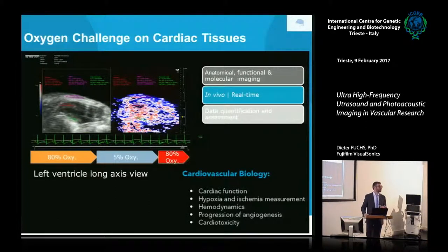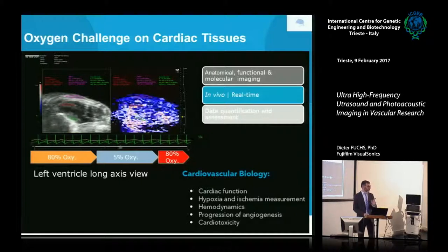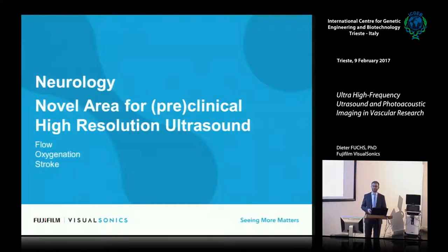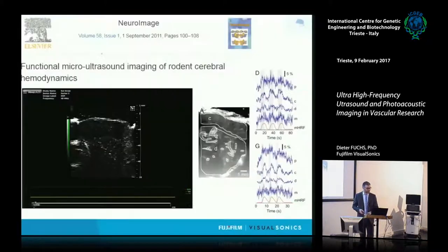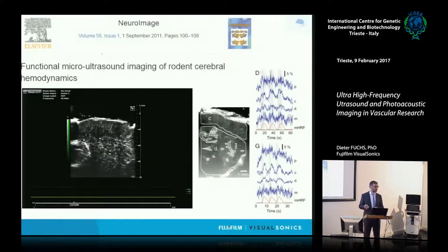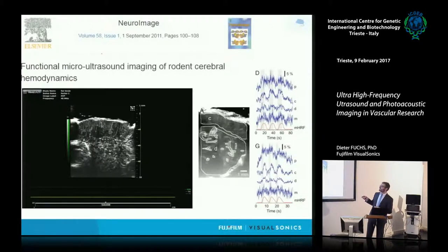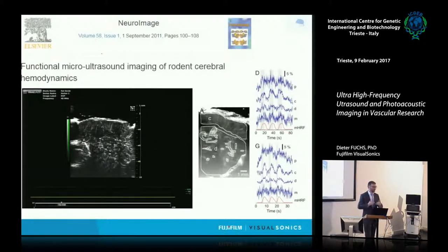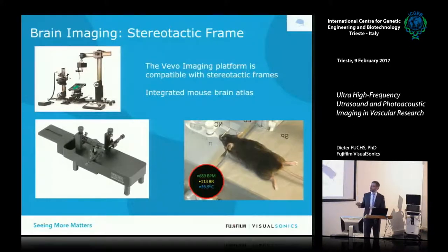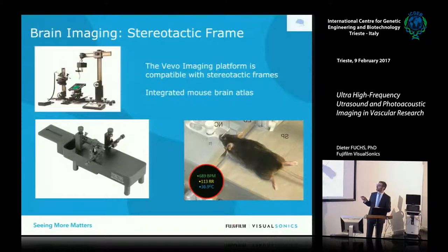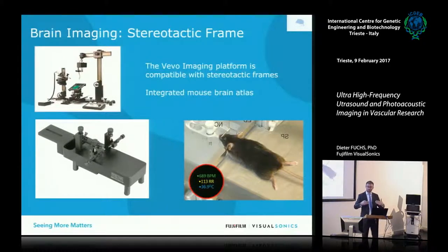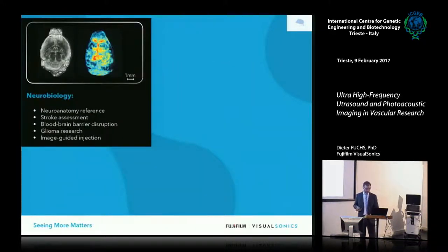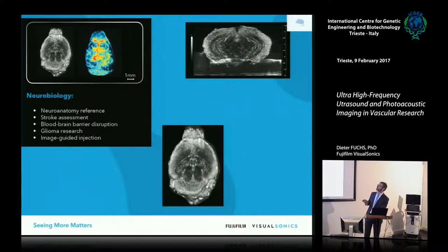How many of you are doing brain neuroimaging? Because that's something we're putting more emphasis on these days as well. It has been shown that with a contrast agent you can get really nice images of the brain — looking at stimulation, in this case a whisker stimulation to see which areas respond with vasodilation. It works fantastically, though the downside is the craniotomy to get the best images. Now, with integration of a stereotactic frame miniaturized to connect to the imaging station, and a mouse brain atlas based on stereotactic coordinates, the system knows where you are so you can make comparisons. You can then do regular grayscale as well as Doppler or photoacoustic imaging on the brain.